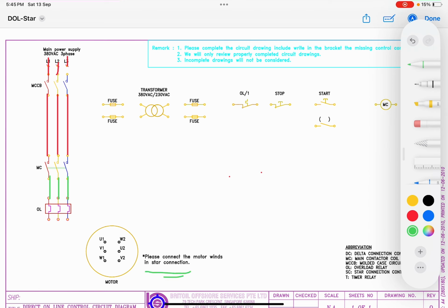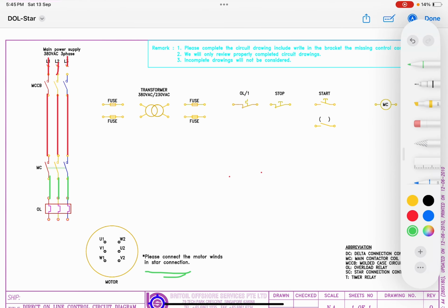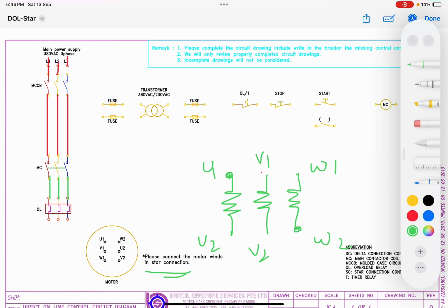Since this motor has to be connected in star, as we know, in star configuration one end of each winding is shorted. Suppose these are the 3 windings of a motor. We can draw like this. If we name this one U1, U2, this one V1, V2, and this one W1, W2. To connect this motor winding in star, we have to short one end of the windings. So here we can short U2, V2 and W2. Once we short these, the power supply coming from the OLR we can connect to the other end of the motor terminals. Once we have connected this, we can see that my motor is connected in star.